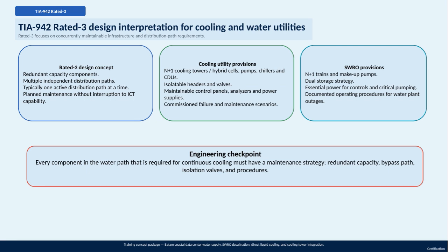Regarding cooling utilities, the design includes N+1 redundancy for cooling towers, hybrid cells, pumps, chillers, and cooling distribution units. The system must have isolatable headers and valves, maintainable control panels, analyzers, and power supplies. Additionally, commissioning failure and maintenance scenarios are essential to ensure reliability. For seawater reverse osmosis, or SWRO provisions, the design incorporates N+1 trains and makeup pumps, a dual storage strategy, and essential backup power for controls and critical pumping. Documented operating procedures for handling water plant outages are also mandatory.